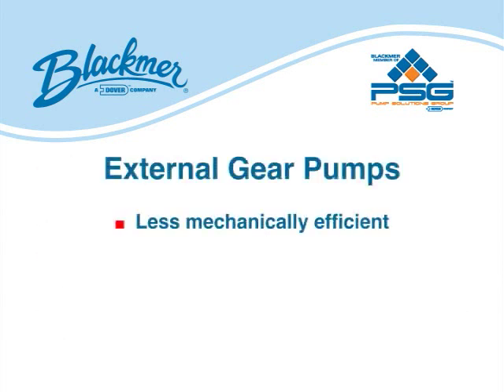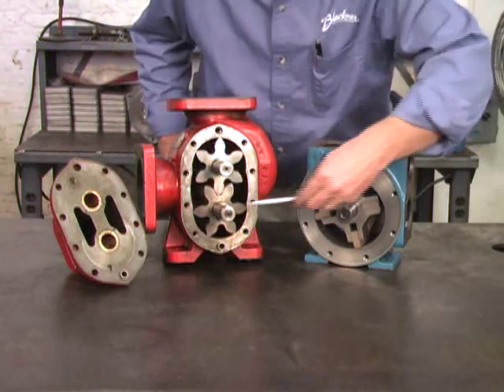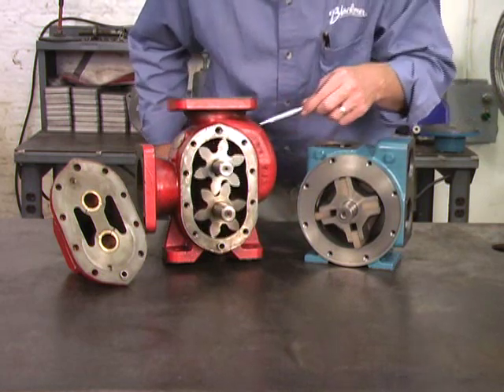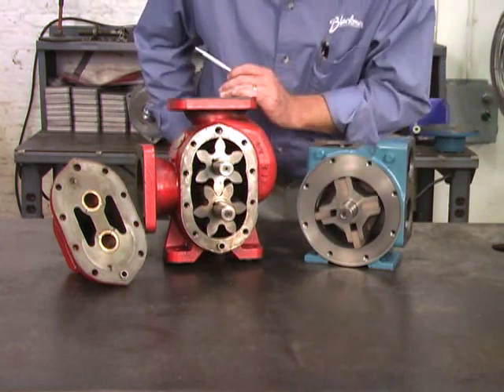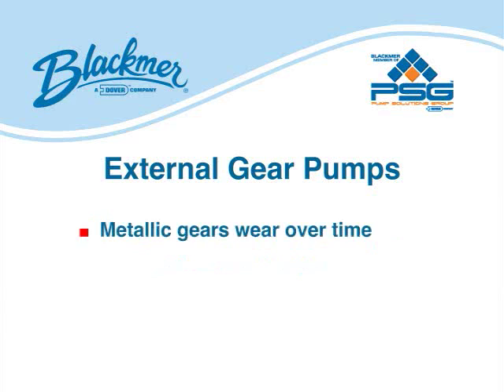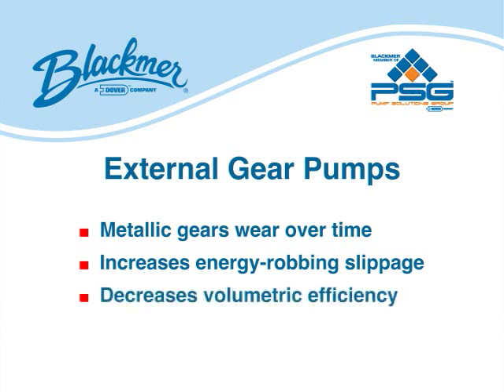External gear pumps are less mechanically efficient than vane pumps and consume more energy. Liquid enters the pump chamber through the inlet port. The pump chamber consists of two rotating metallic gears. As the gears rotate and come out of mesh, they create a void. The volumes are reduced and liquid is forced out the discharge port. Each revolution displaces a constant volume of liquid. Variances in pressure have minimal effect on pumping performance. However, because the gears actually cut the liquid as it enters the pump chamber, gear pumps should not be considered for moving shear-sensitive liquids. The metallic gears wear over time, resulting in wider clearances.